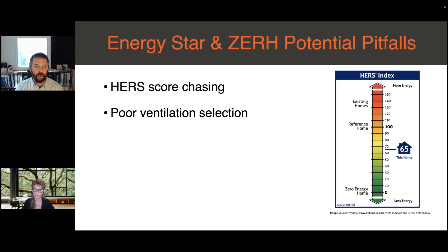Poor ventilation selection is another pitfall. Blanket statements on ventilation systems across different climates and humidity zones are often made by product manufacturers, program documents, and increasingly by social media influencers who often get money from some of those product manufacturers. We need to make sure we're picking the right ventilation system for the right climate, and that these ventilation system controls are appropriately functioning with our heating and cooling controls as well.